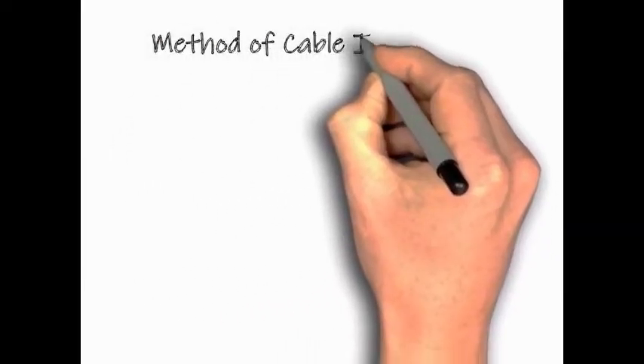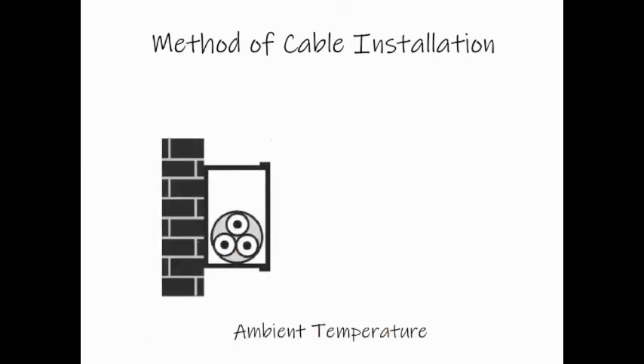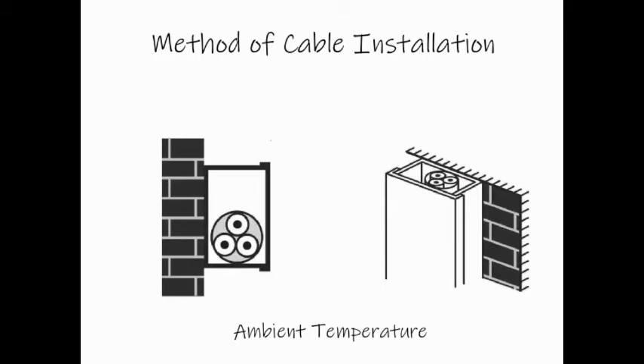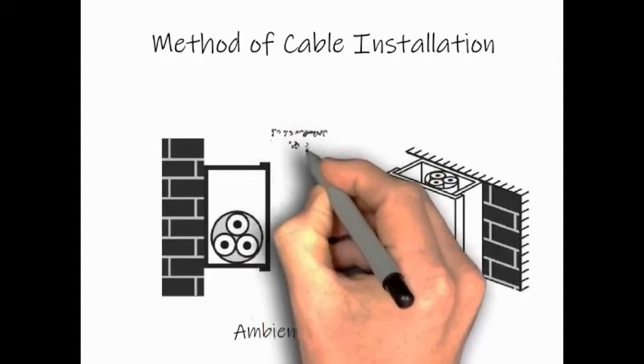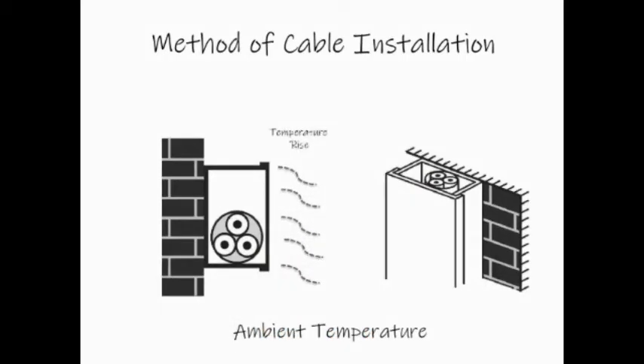The second factor that affects voltage drop is the method of cable installation. The method of installation of cable affects the current carrying capacity. The key reason is because of ambient temperature. And this means the method of installation. With an example of a cable housed in the trunking, how the cables are grouped together and the type of thermal insulation material being used plays a significant factor in affecting the overall temperature. If there's a rise in temperature surrounding the cable, this will affect the correction factor.